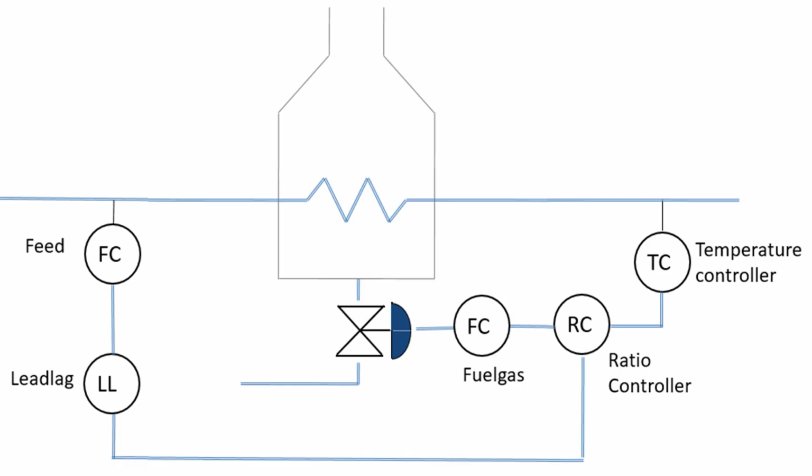The furnace is controlled in terms of temperature by adjusting the fuel, but the feed is upstream, so that gives us an advantage to know the feed, what it will be before it arrives at the furnace. Because it's upstream, we have to delay it to bring it in phase with the fuel changes, and the way we can do that is using a dead time and lead lag algorithm.